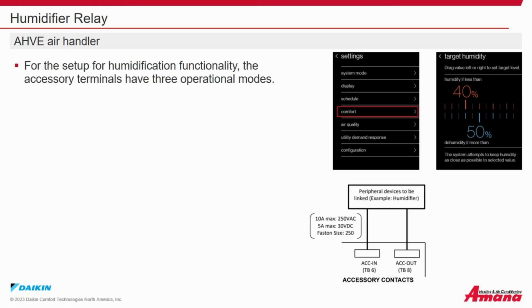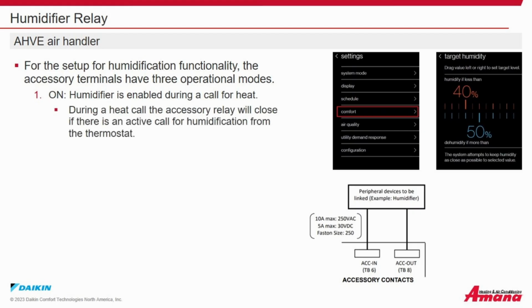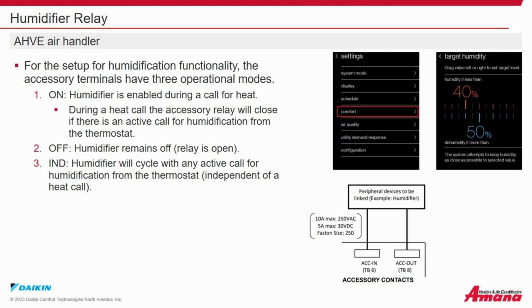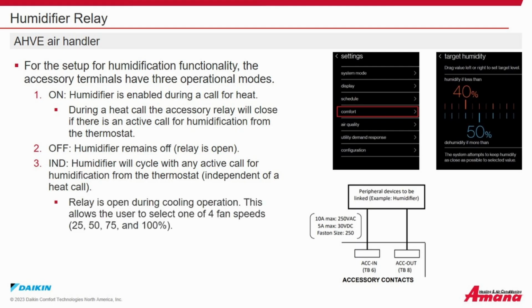Humidifier relay. On an AHVE air handler, for the setup for humidification functionality, the accessory terminals have 3 operational modes. 1. On, which means the humidifier is enabled during a call for heat. So during a call for heat, the accessory relay will close if there is an active call for humidification from the thermostat. 2. Off. Humidifier remains off, the relay is open. 3. Independent. The humidifier will cycle with any active call for humidification from the thermostat, independent of a call for heat. The relay is open during a cooling operation.